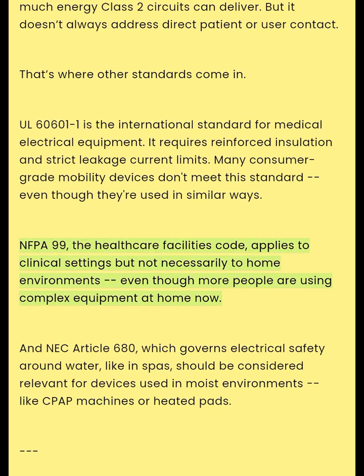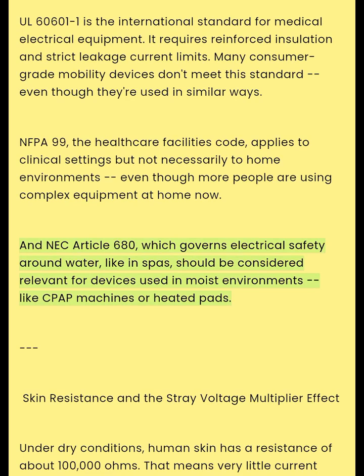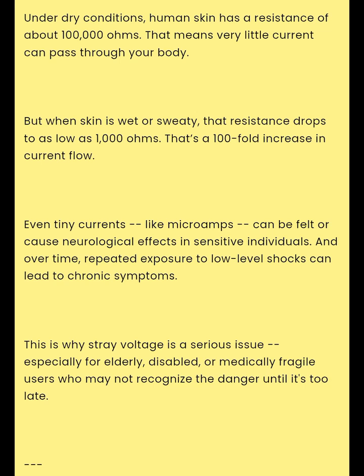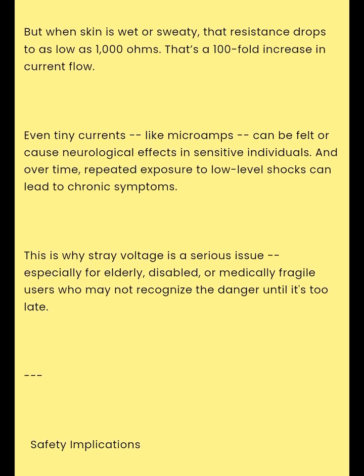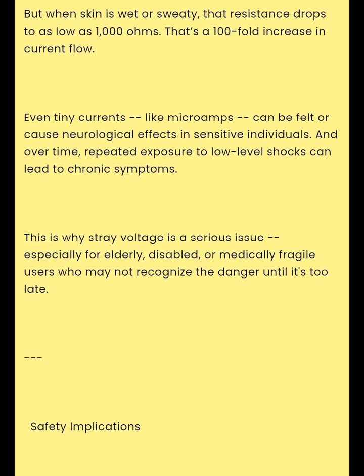NFPA 99, the Healthcare Facilities Code, applies to clinical settings, but not necessarily to home environments, even though more people are using complex equipment at home now. And NEC Article 680, which governs electrical safety around water, like in spas, should be considered relevant for devices used in moist environments, like CPAP machines or heated pads. Skin resistance and the stray voltage multiplier effect. Under dry conditions, human skin has a resistance of about 100,000 ohms. That means very little current can pass through your body. But when skin is wet or sweaty, that resistance drops to as low as 1,000 ohms. That's a 100-fold increase in current flow.